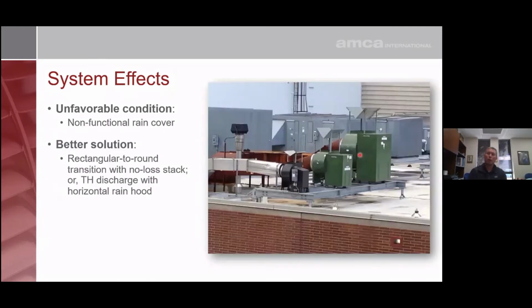I was walking through a parking lot in Chicago one day, leaving the ASHRAE trade show, and I saw these fans. I had no idea why they decided to use these types of hoods to try to keep rain out of the fan. I think some architect designed them, not a very good design. Rain typically falls at an angle. Sorry if there's architects out there. Rain falls at an angle, very seldom vertically. It doesn't take much of an angle for the rain to get back into the fan. No straight runs of ductwork for static pressure regain. They really don't serve any function other than they look kind of cute.